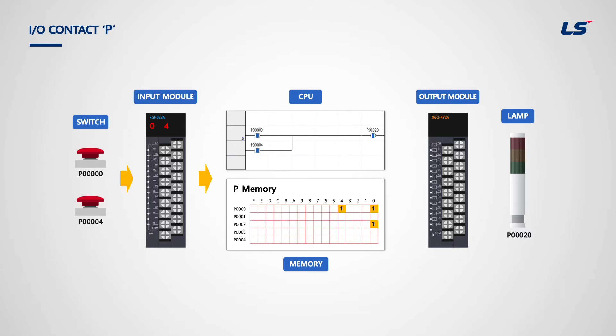As you can see from the picture in the center, the first row of word P0000 is composed of 16 bits from P00 to P0F. As the ladder program is written, when P0 and P4 bits are on, bit P20 on the output module is also turned on. Modules other than digital input and output do not use P memory.